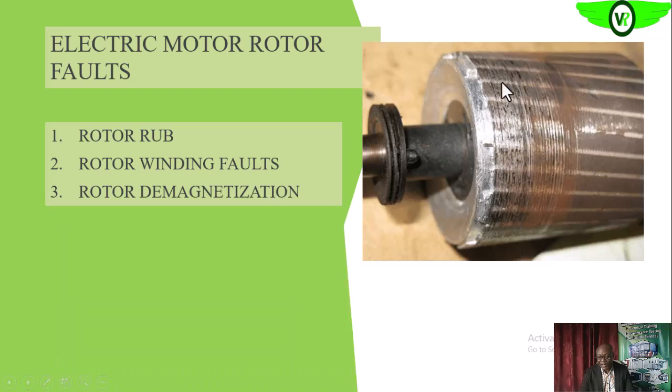Apart from eating up the rotor bars and the yoke of the rotor, this is the yoke, it is reducing the effective size. And remember, this yoke is meant to concentrate the magnetic field, that is, to increase the strength of the magnetic field in the area where you want it to be focused.